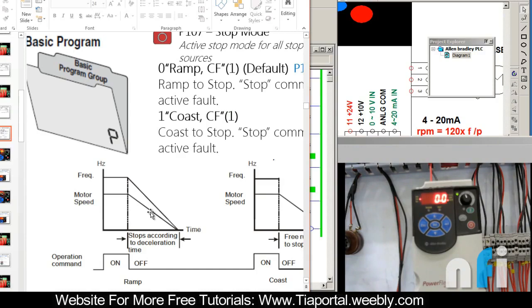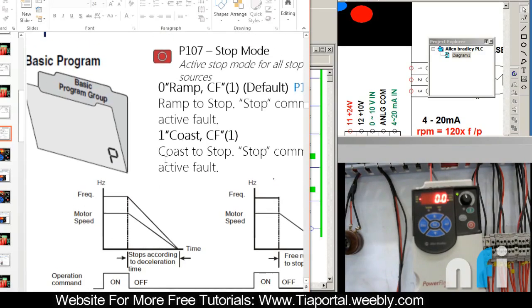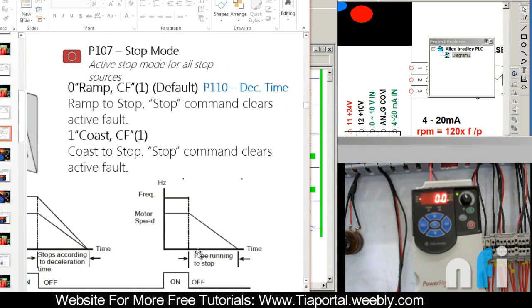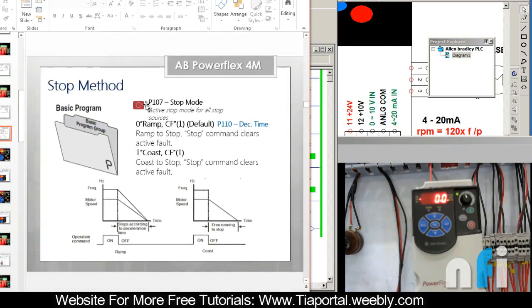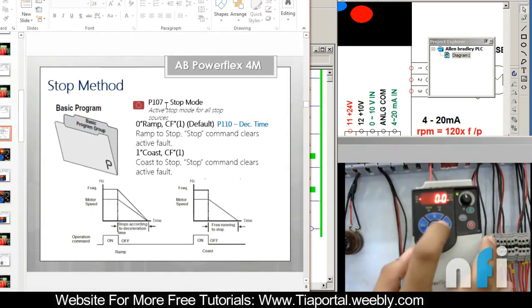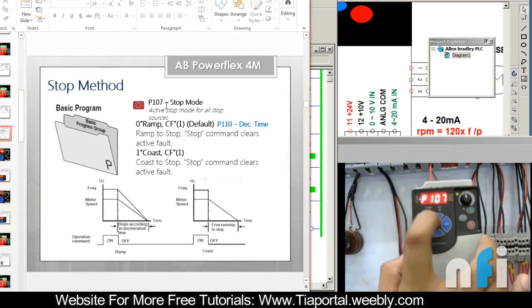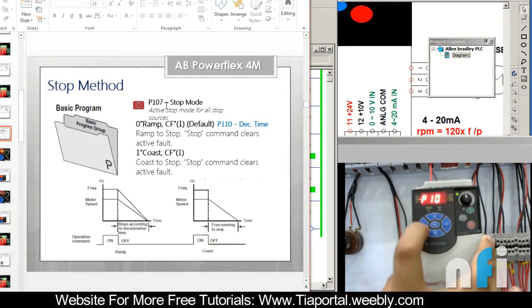That's called a ramp stop. The other one is coast stop in which the drive will shut off immediately but the motor will keep on running and stop by its own inertia. By default the drive is at ramp stop, that is defined in parameter 107. Let's see what is in that by default. It's zero, so it is ramp stop.